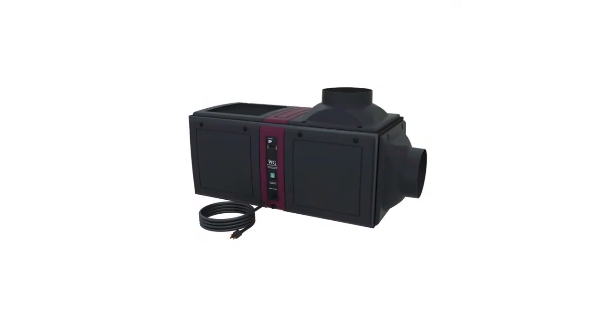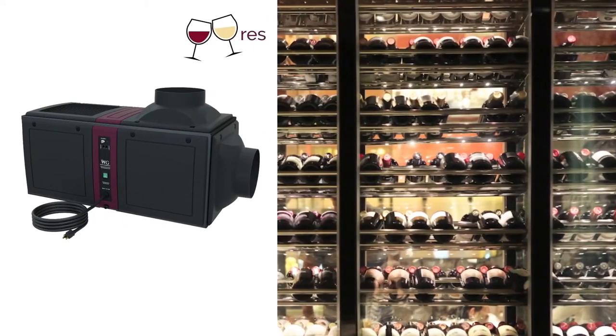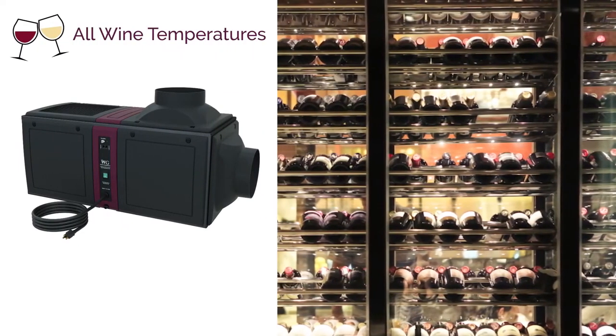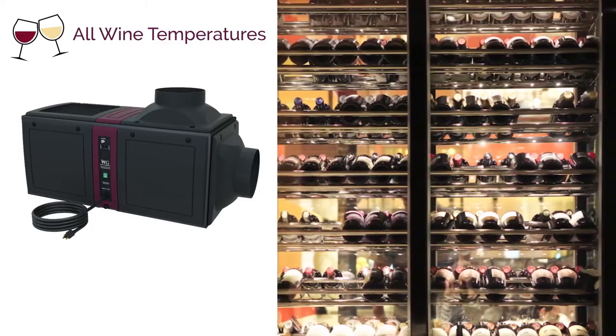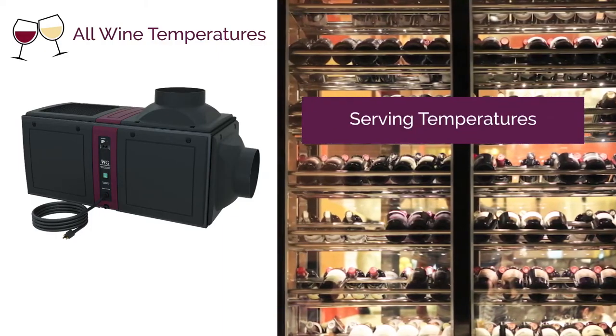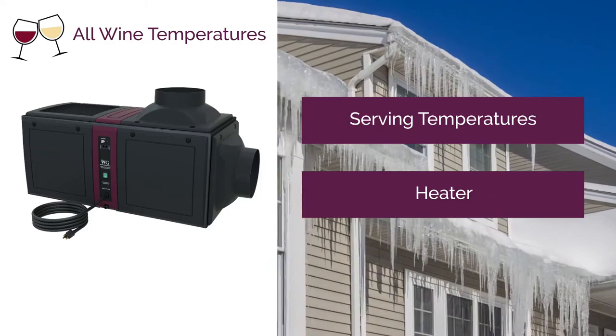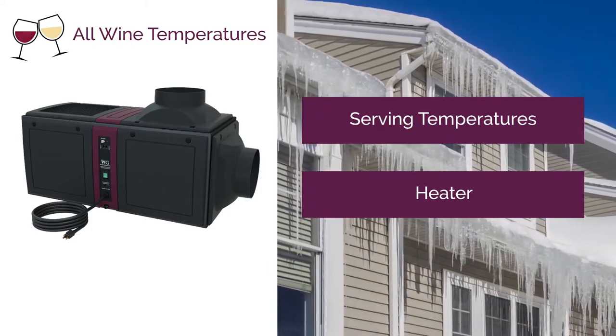The ducted self-contained unit, as you see here, is a base system. We do have several options available to us in bundled formats, depending on your application, to help better control the device and meet your application needs. The first option available is the all wine temperature bundle. You would choose the all wine temperature bundle if you wanted to control your cellar to wine serving temperatures. The bundle also contains a heater in the system to protect the wine cellar from dangerously low temperatures.